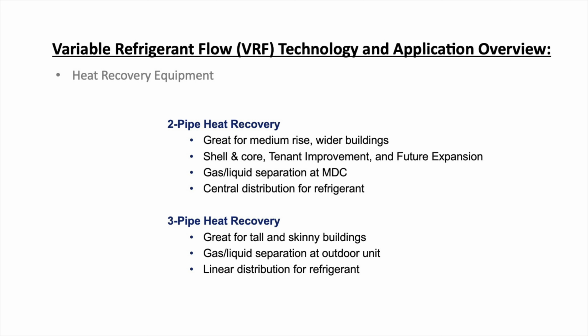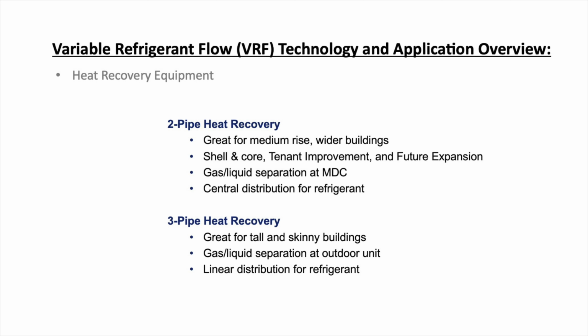TI and shell and core buildings can also be good candidates for a 2-pipe heat recovery system. So say you have a building that has multiple tenants and they're not all filled out once the building is turned over. You can cap all those pipes coming from the MDC and add future equipment as future tenants move in. You can also do this in a 3-pipe heat recovery system. You can also use 3-pipe heat recovery for taller, skinnier buildings. Mid-rise to high-rise office buildings, hotels would be good candidates for 3-pipe heat recovery.